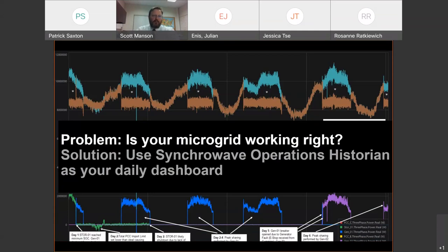And this is the number one heads up display that the operations team now uses on our jobs. This is the first place you look when you're wondering, is your microgrid working right? And this data all comes from relays, because relays are right there in the site, they're in the substation, they're everywhere, and they have all the data you need to populate your historian. You don't need meters, you don't need extra CTs, you don't need extra computers, and you can save a lot of cost and a lot of complexity using systems like this.